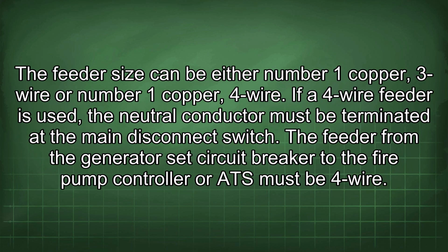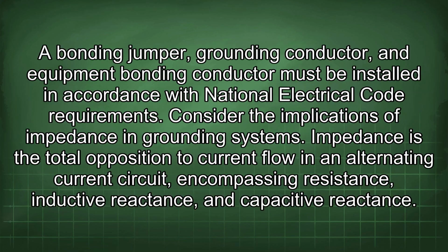The feeder size can be either number 1 copper, 3-wire, or number 1 copper, 4-wire. If a 4-wire feeder is used, the neutral conductor must be terminated at the main disconnect switch. The feeder from the generator set circuit breaker to the fire pump controller or ATS must be 4-wire. A bonding jumper, grounding conductor, and equipment bonding conductor must be installed in accordance with National Electrical Code requirements.